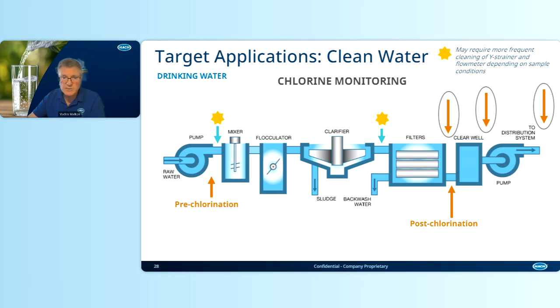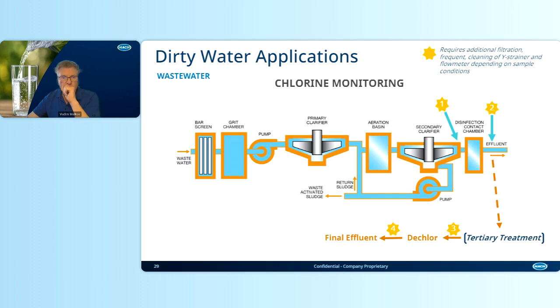Now, those applications depicted by the stars may require more frequent cleaning of the Y-strainer and the flow meter, depending on the sample conditions. Moving on to the other applications, such as dirty water applications. The first example, of course, is wastewater, and first of all, municipal wastewater. So the instrument can and should be used in the effluent, and particularly the tertiary effluent, which is normally filtered wastewater. It is one of the possible and very reliable applications for the CL17SC.